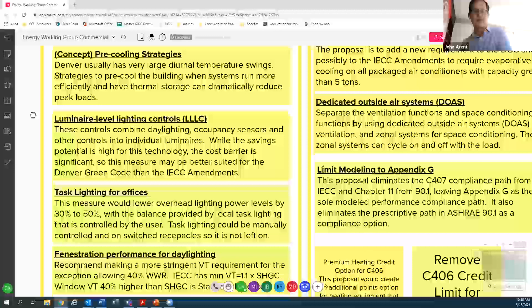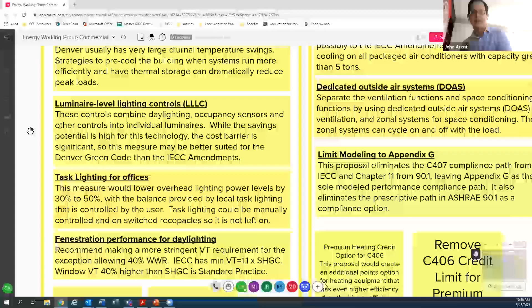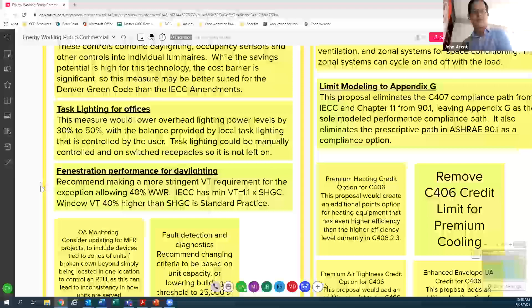You can scroll down a little, Erica, toward fenestration performance. This is a pretty minor one. The IECC has a minimum visible transmittance of 1.1 times the solar heat gain coefficient, SHGC. I think standard practice for using windows to provide daylighting can achieve higher visible transmittance, so the recommendation here, a minor change, would be to change that 1.1 to a higher value, such as 1.4, or have a minimum VT of 0.4 for the glazing.